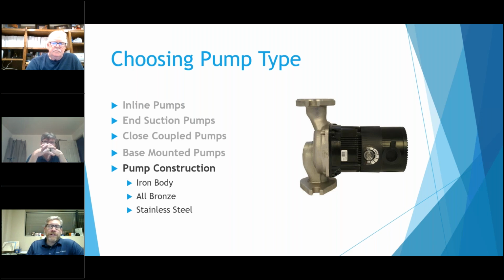The other thing that we see them on is pressure boosters. A lot of people like to use stainless steel on there. We used to use a lot of cast iron pumps, and some still use a coated cast iron body. On pressure boosters, the reason you can use that is that in that application the water is cold, and it doesn't necessarily attack the cast iron body, but it actually gives it a coating. If it were hot water, it would certainly have a lot of problems with using an iron body, but people have kind of gotten away from that. They don't want the cast iron body, so they've gone to stainless steel fitted pumps or stainless steel pumps.